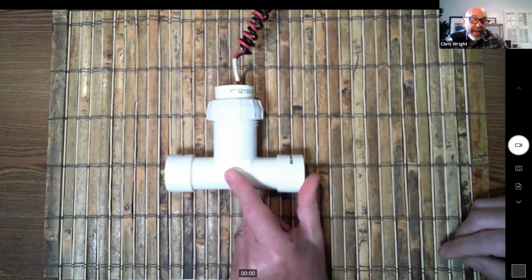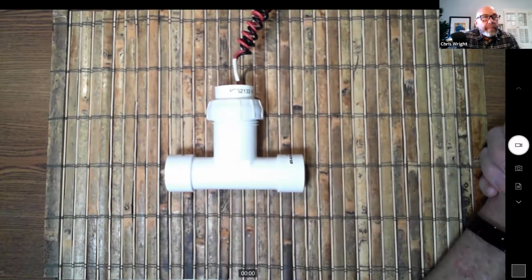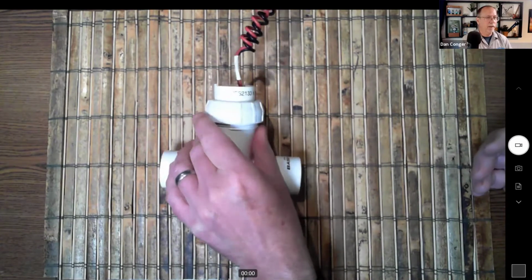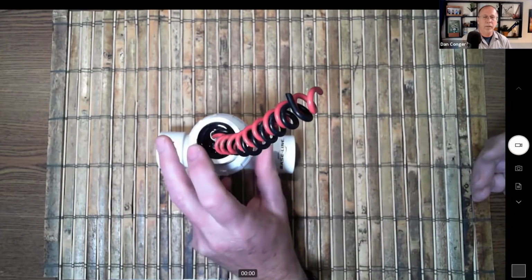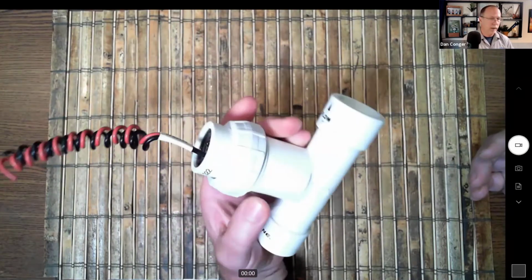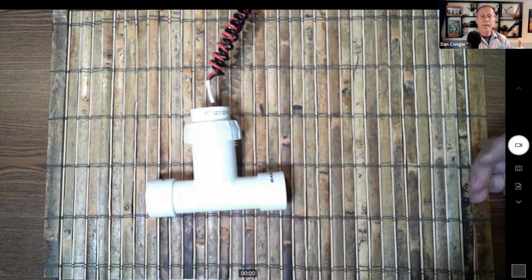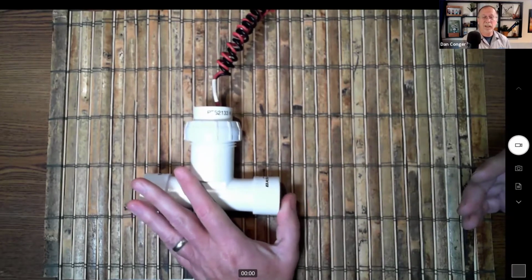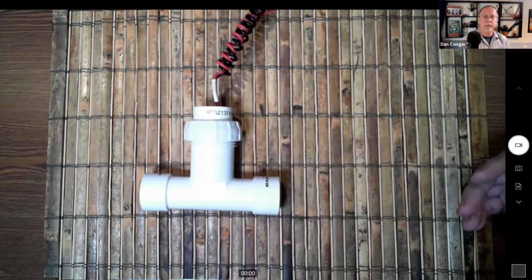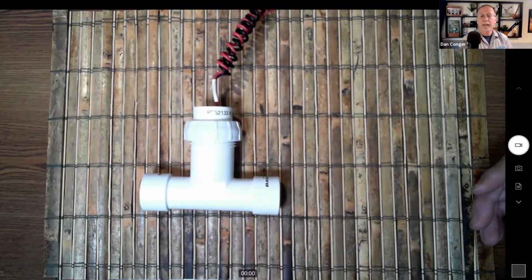Okay. So if you're using that, you've installed that on your main line or at a control point. How do you know if it's set up correctly? Well, the nice thing about this is because it has that flow bicoder built into it, it's pre-programmed with the K value and the offset value. So once I bring this serial number into the controller, I will be able to see in the control point settings that those values are in there and it's ready to roll. It's always a good idea, though, to do some sort of reality check, because I have seen times when K values are wrong and the flow value is not correct, not necessarily because someone's played around with it.